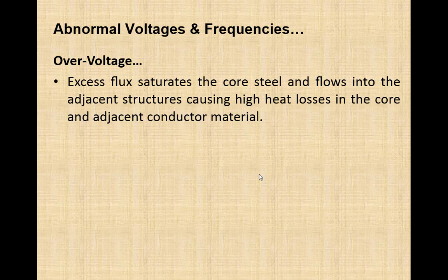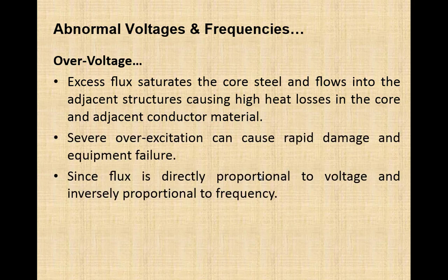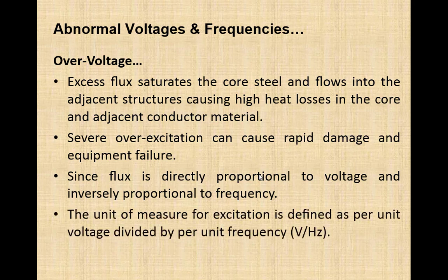Now overexcitation is due to over voltages. Here we discuss this overexcitation problem a little more. Since flux is directly proportional to voltage and inversely proportional to frequency, the unit of measure for excitation is defined as per unit voltage divided by per unit frequency.